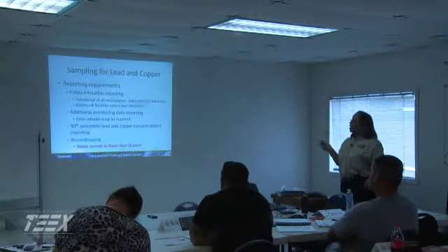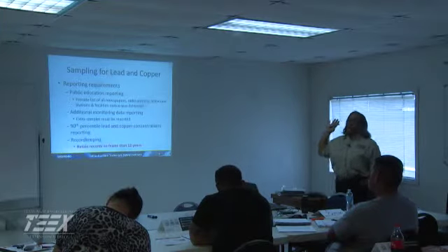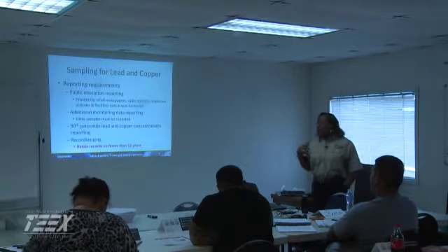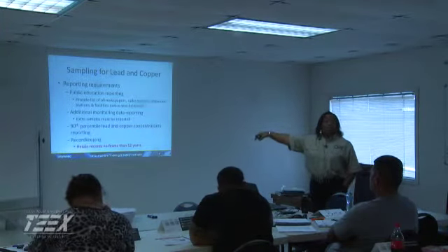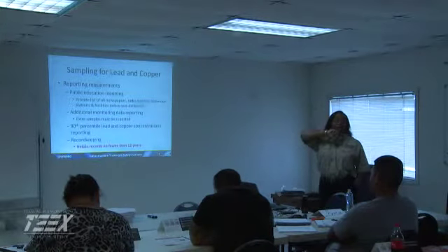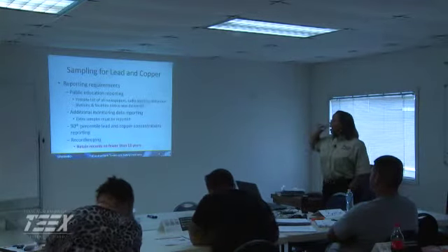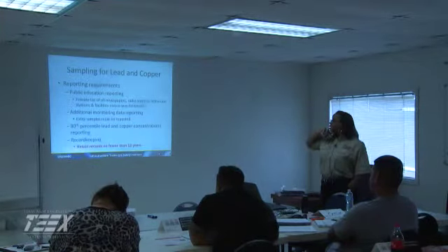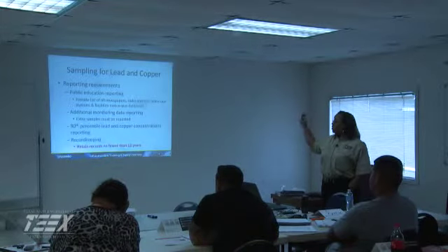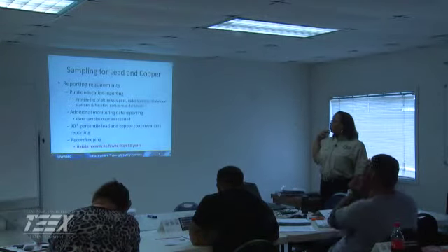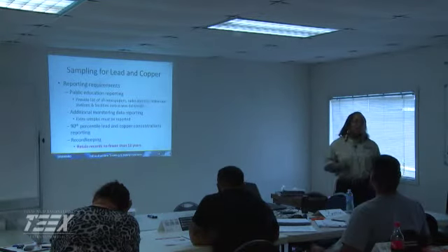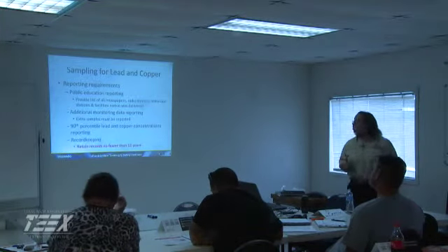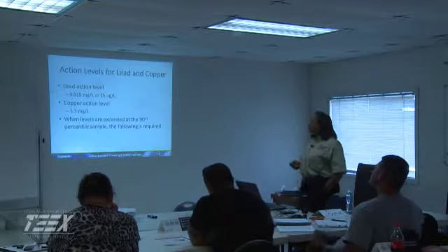Okay, record keeping. Now all this stuff that we keep telling you that you got to report. Not only do you have to report, but you got to retain records. 12 years for lead and copper as far as your retention. When you're doing the public education, make sure you're providing the list of all newspaper, radio stations, television station facilities where the notice was delivered. And they have to keep running that notice until, again, your numbers are back within range and it can be lifted. Okay.